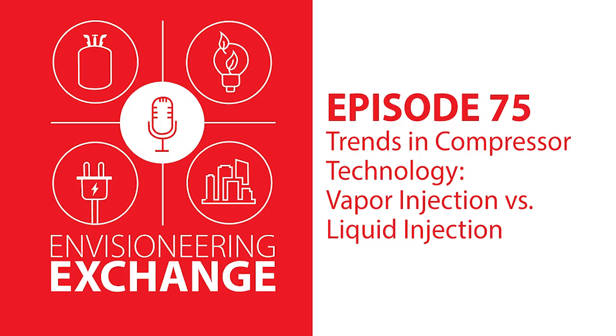Are injection systems available with both fixed speed and variable speed compressors? Yeah, so everything started, of course, with fixed speed. Fixed speed compressors, single compressors, and then you can do tandems or trios to size up the system and capacity. So that's where it all began for us and also other manufacturers. But what we're seeing now is a lot of push to variable speed compressors, particularly for units like DOAS units, where they mostly use variable speed compressors as the heart of their system.